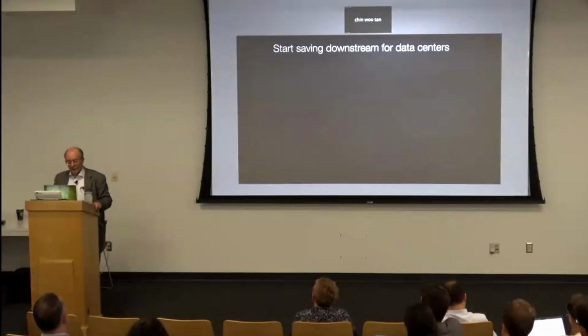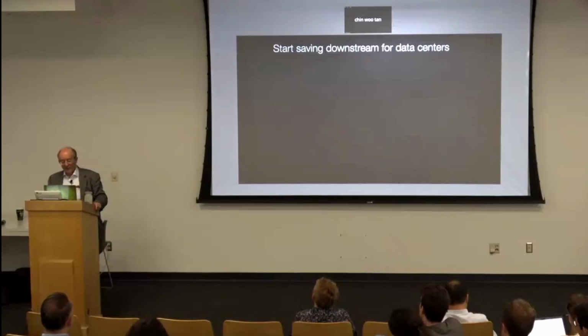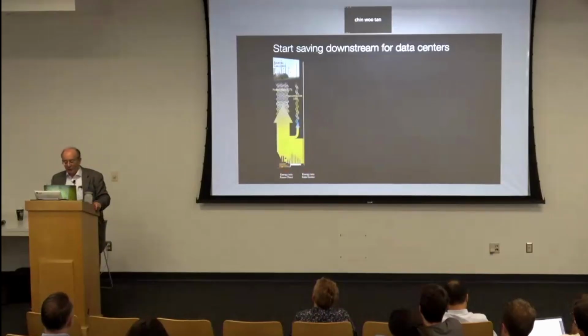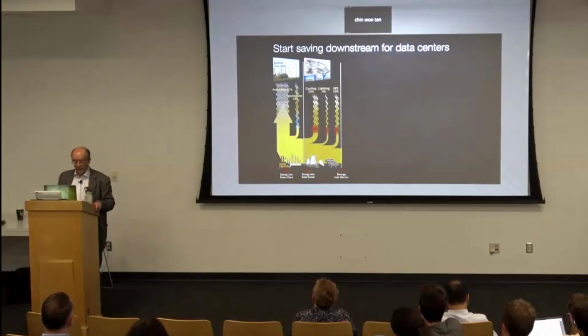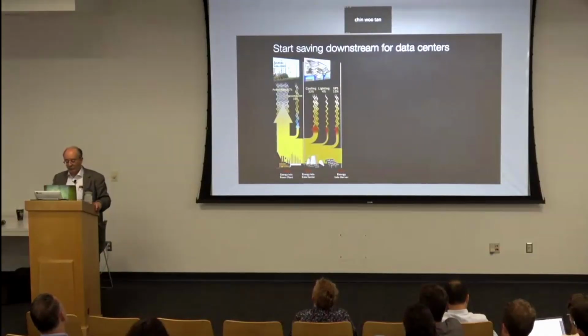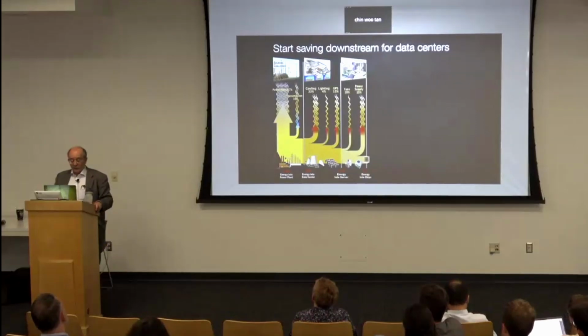Now let's apply the pumping system logic to big old data centers. Two-thirds of the fuel fed into the power plant is lost to the plant and the grid. Half the metered electricity is lost to the cooling system and the uninterruptible power supplies before reaching the servers. Half the server energy doesn't reach the chips because it gets lost first in inefficient, usually very underloaded power supplies and lots of superfluous fans.